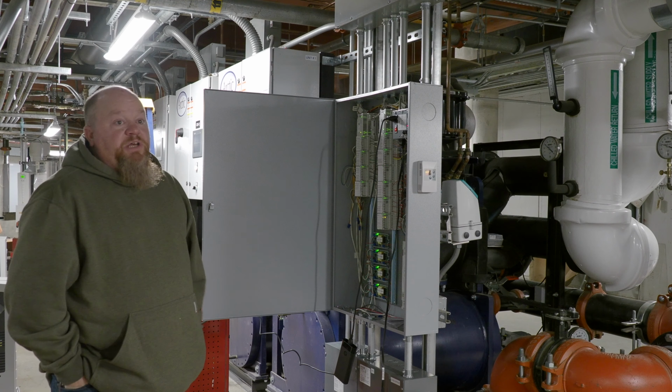So the inside here is a PXCM. There's also communications from here to each of the 4 chillers. This controller also communicates to the DEMs on the main switchgear and your ATSs for your generator. It's kind of the same as our old FLN, but it's BACnet MSTP. Master, slave, token passing. MSTP.